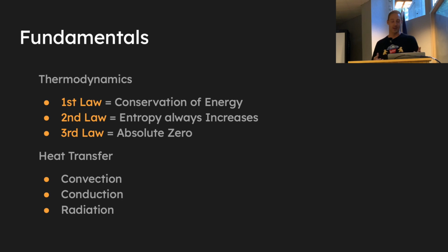And then in the context of Bitcoin mining, conservation of energy, like if you have 1 megawatt of electric energy flowing into your Bitcoin miners, that means you have 1 megawatt of heat to dissipate. You got to reject it, and you have to reject it at the same rate that you're consuming it to be steady state. Otherwise, you would have what's called a transient system, where if you're not rejecting 1 megawatt, but you're consuming 1 megawatt, then you're heating up, right? That heat's not being rejected at a fast enough rate. So conservation of energy.